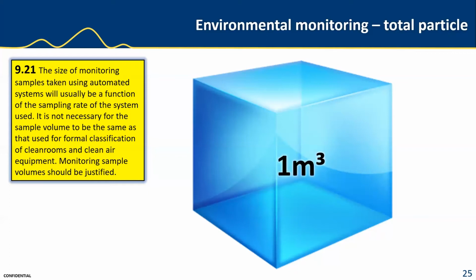Here we see a volume of a cubic meter, and then we look at the volume of a cubic foot. There's a huge difference between the two. And the sample rate of a remote particle counter is typically 1 CFM. And we've seen in guideline 9.21, the exception is that the remote particle counter should sample 1 CFM. And the sample rate is based on 1 minute intervals. So as long as you use 1 CFM remotes, then you are within expected practices. Now I'm not saying that 0.1 CFM remotes may not be used. If you do use them, then you will need to justify them. You're taking less of a sample with 0.1 CFM. And you usually find 0.1 CFM in handheld units. There are some remotes that are available with 0.1 CFM.